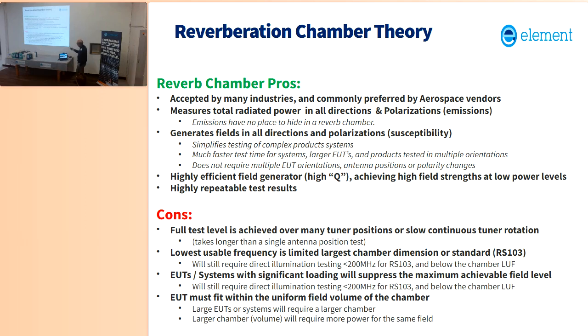Cons: a full test is achieved over many tuner positions. So if you've got a simple box and you're only going to test one antenna location right out in front of the box, it's going to take you longer to do it in a reverb chamber as compared to the anechoic chamber. It'll take longer. I think it's a better test than the anechoic chamber, but still, you can run the test according to DO-160. Anechoic is faster. If you've got a single box you're only going to test one side of it. Now you're probably dumb to test only one side, or maybe you're not. I don't know, because I guess it costs less money.